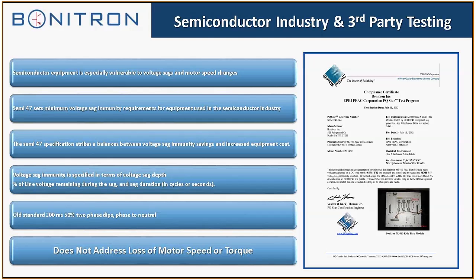We just got through testing the SAG ride-through with compressors, and it's a special type of a super compressor, so to speak, and we hook up the ride-through to the inverter section of the combination inverter compressor motor. It's one combination unit. We did testing on that, and now it's become a popular solution for critical refrigeration, where you can't have any change in the compressor speed or the compressor output.